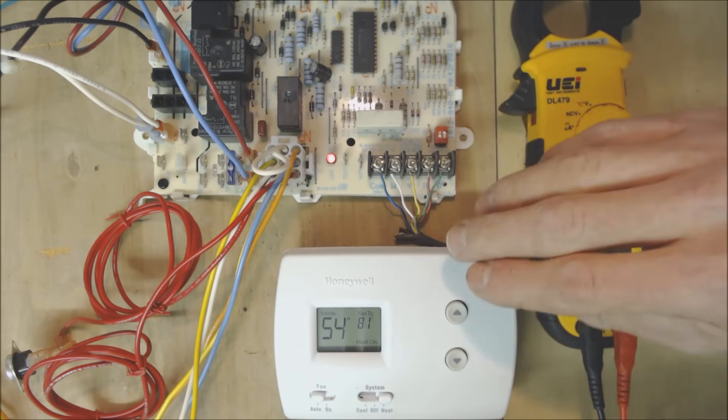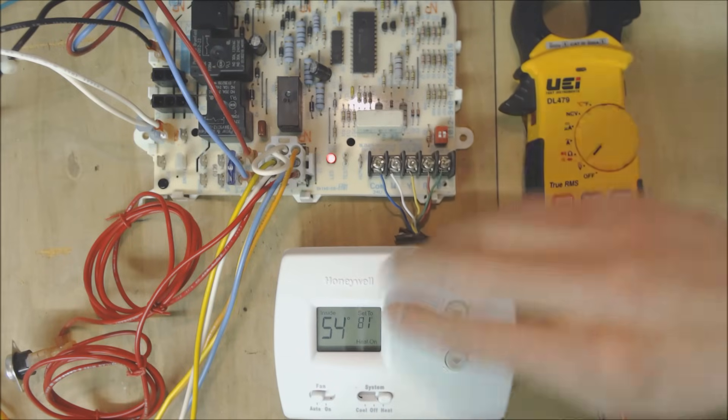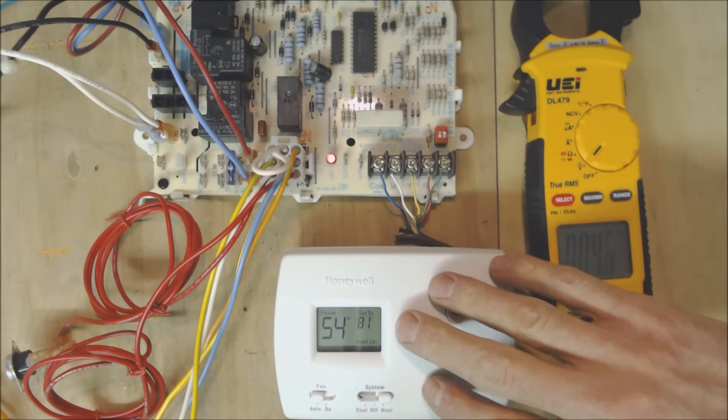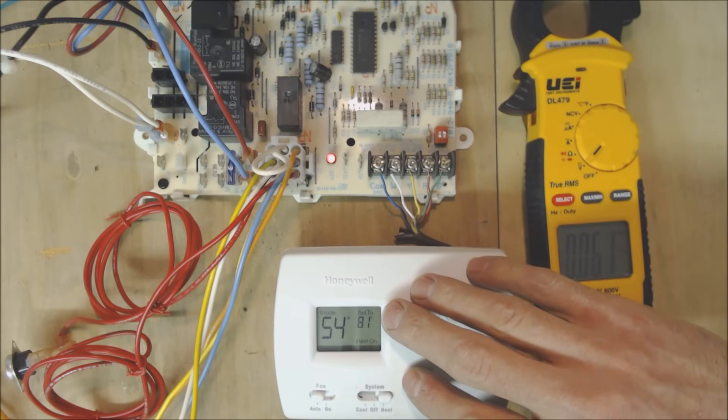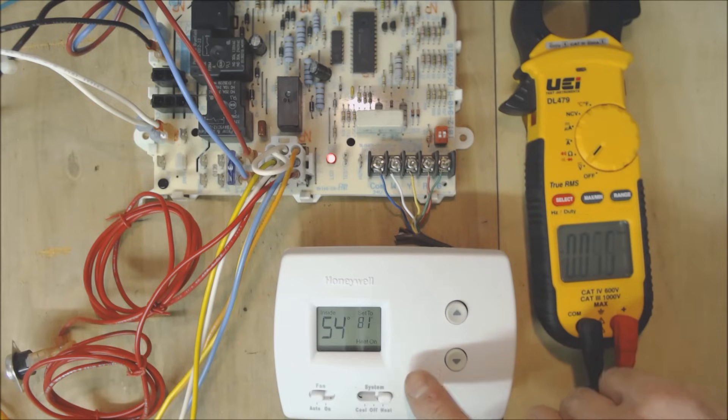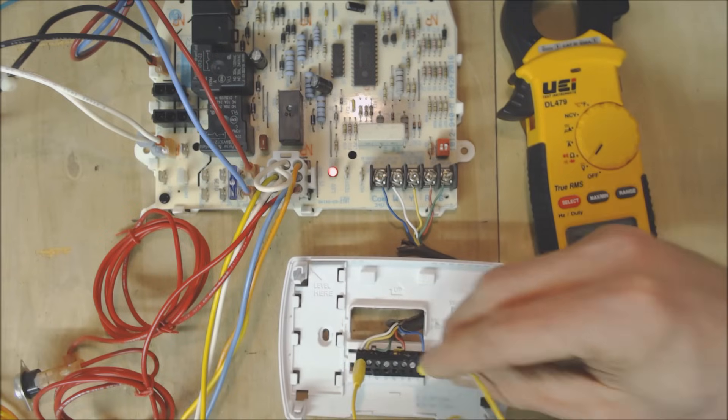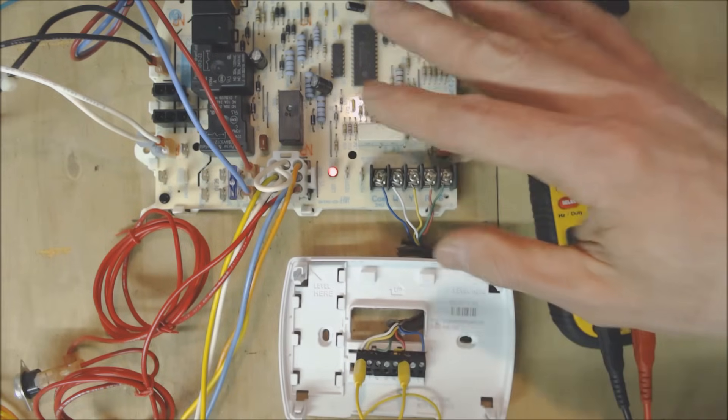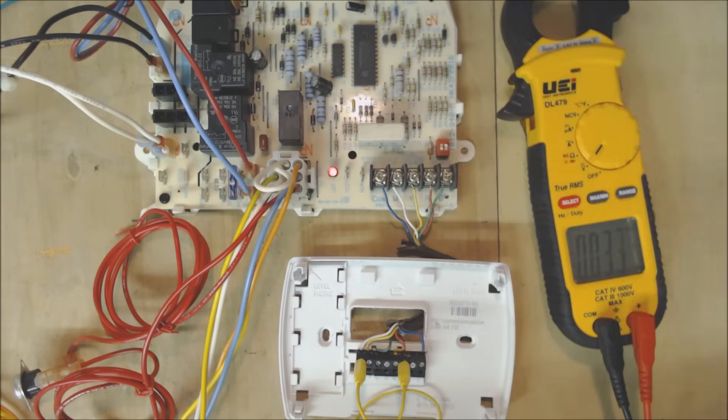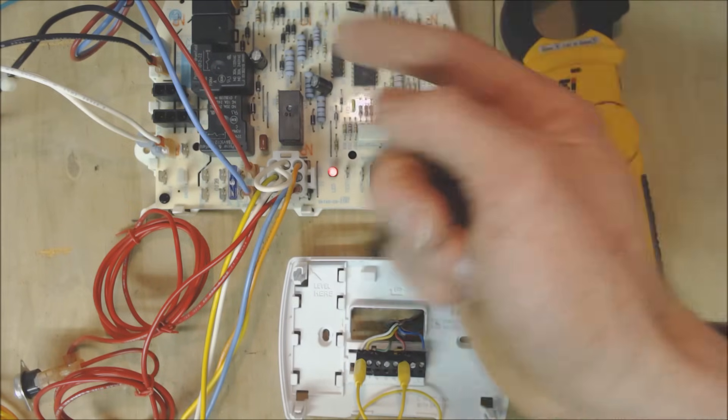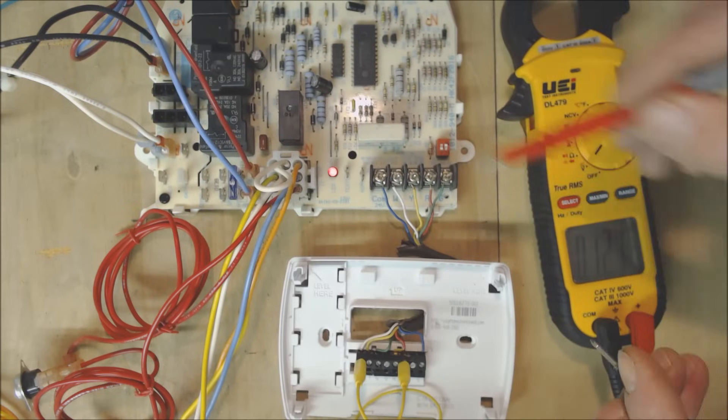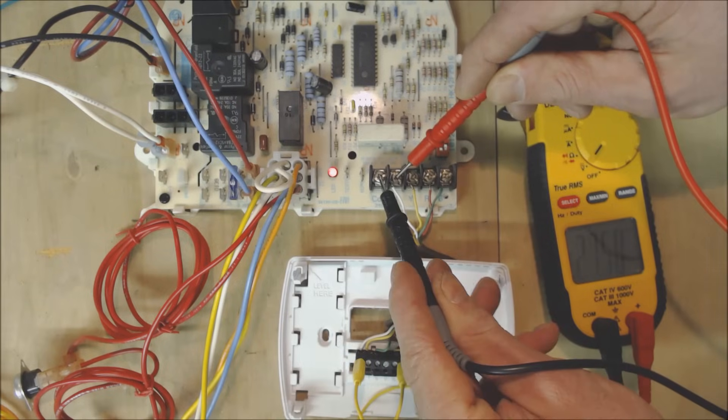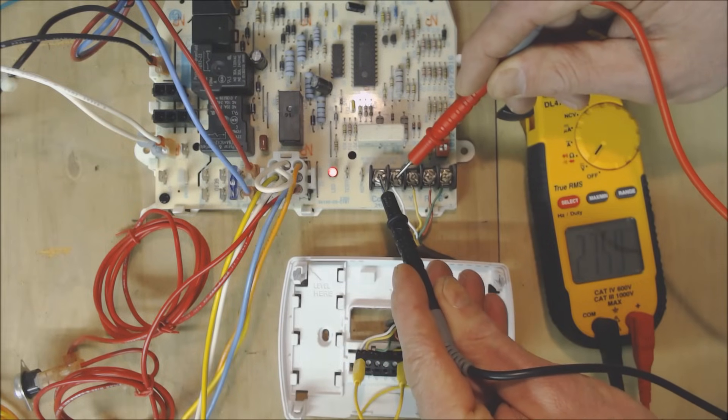In this case you'd either have a problem with your thermostat itself or the thermostat wires and the way to determine if it's the thermostat face is what you could do is take the face off and then jumper from W to R and see if you have the same problem. So if we jumper from W to R then that should tell heat to turn on. And the first thing that happens in the sequence of operation for the furnace is that the control board is going to send power to the inducer motor. So now we can go ahead and check our voltage. We can check from W to C and you see that now we have 27 volts.